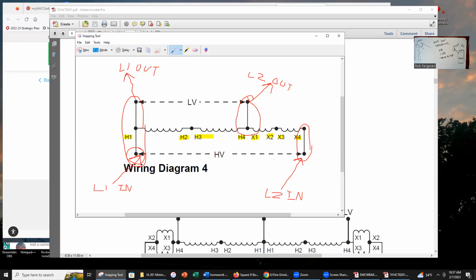But because this is a flexible use transformer, I also need to wire nut together X2 and X3, and also wire nut together H2 and H3. By wire nutting those little jumpers together, it creates the circuit that gives me that full 32 volt voltage reduction. So this is how I would select and also wire up, in this case, a buck or voltage reducing transformer.